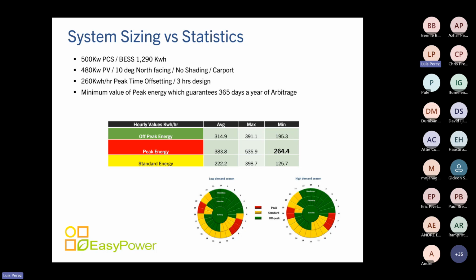In other words, in this complex, which is a residential complex, you have different energy utilization in winter and summer and during holidays. What you're trying to achieve here is that the energy traded with the grid and back with the tenants—those cycles happen with exactly the same amount of energy, 2 times per day, 365 days a year. In other words, you will not have energy in your battery you cannot sell to your tenants, because that would lead to a very large battery system, but neither do you want too small a battery system.